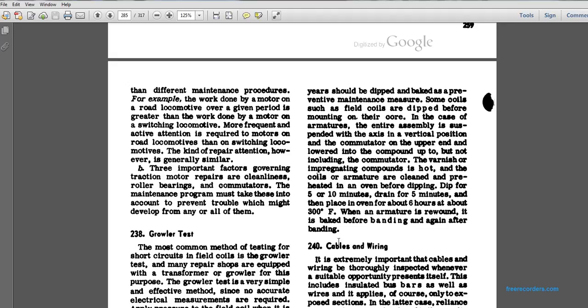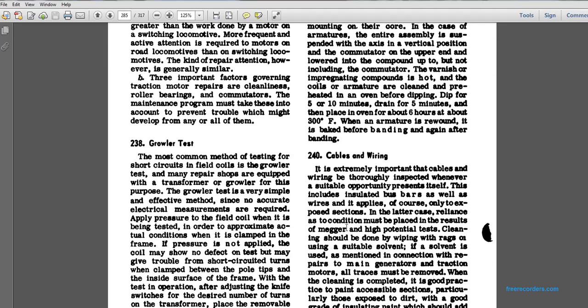The varnish impregnating compound is hot. The coils and armatures are cleaned and preheated in the oven before dipping. Dipping is 5 to 10 minutes, draining is 5 minutes, then they are placed in the oven for 6 hours at 300 degrees Fahrenheit. The armature is then rebanded and baked again after the banding.